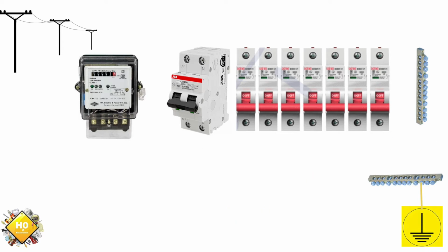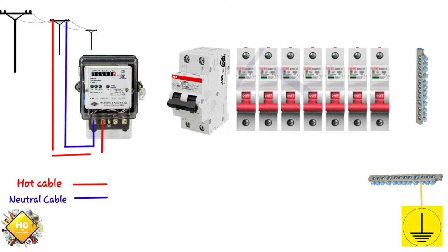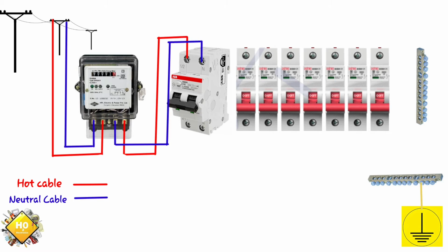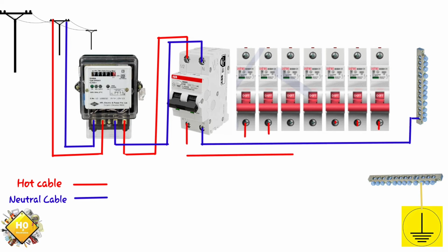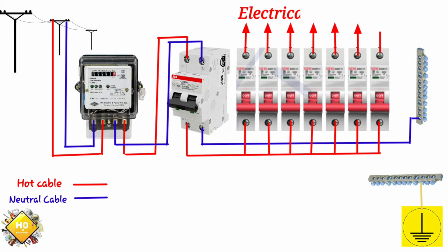Now let's drop live and neutral cables to the electric meter. Connect the cables from the meter to the double pole MCB. Connect the neutral cable to the neutral bus bar. Connect the live cable to the circuit breakers by looping. The outgoing of the circuit breakers are connected to the sub-circuits, final sub-circuits, and electrical devices and appliances. Neutral and earth are also connected to the sub-circuits, final sub-circuits, and electrical devices and appliances.